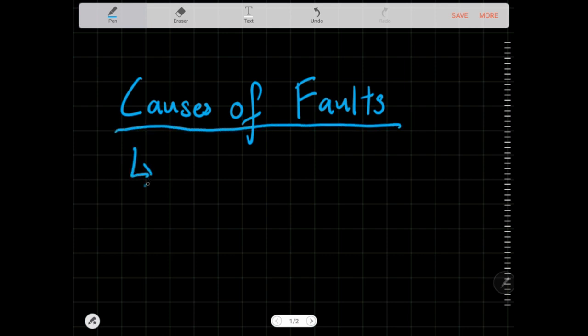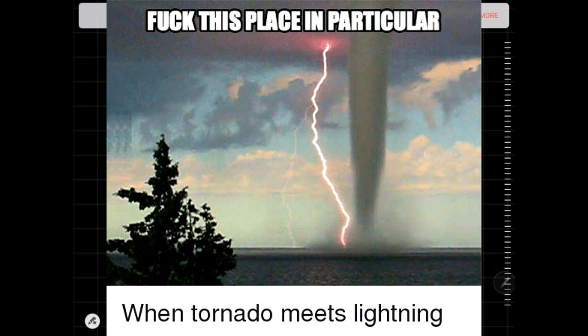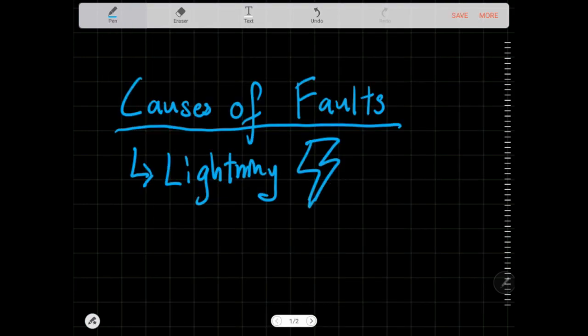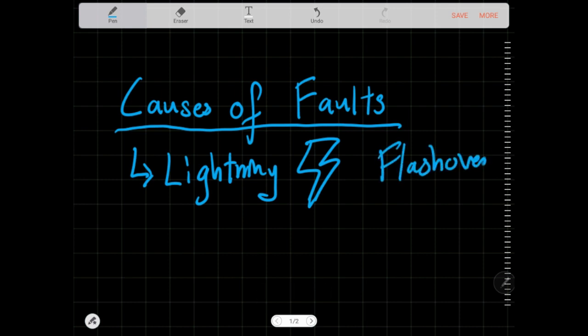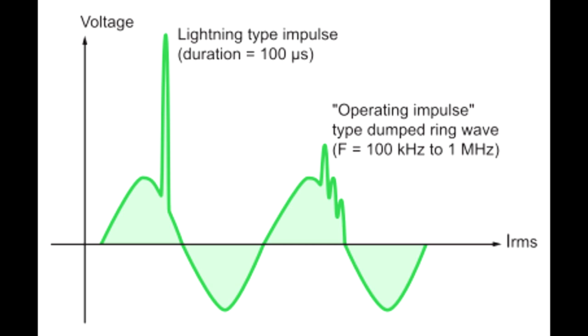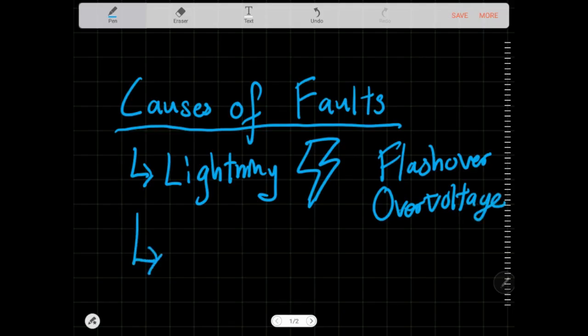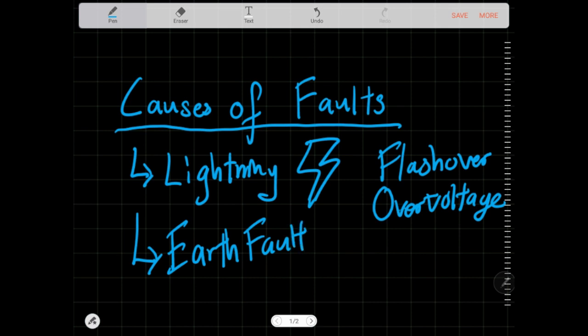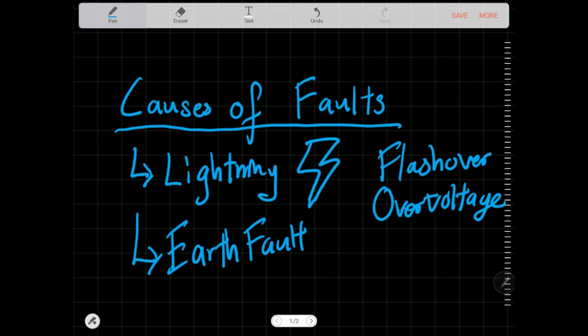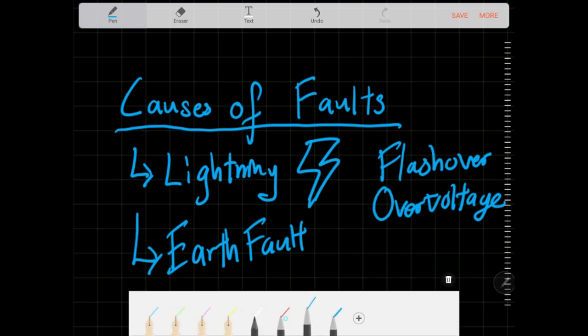Let's look at some causes of faults. Lightning can cause faults in the power system if it strikes onto open bare conductors — overvoltage can happen, flashover can happen, and those are called faults. There are also earth faults, which occur when a transmission line is touched by an object that grounds the line to earth. The main difference is that lightning is more of a transient fault by nature.